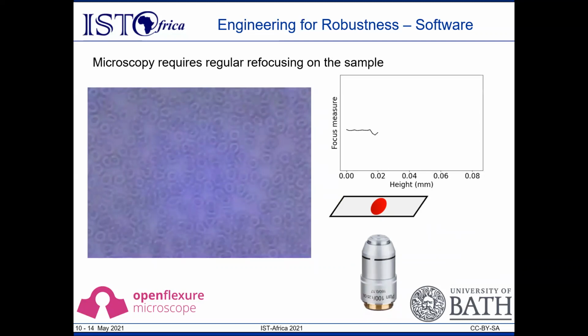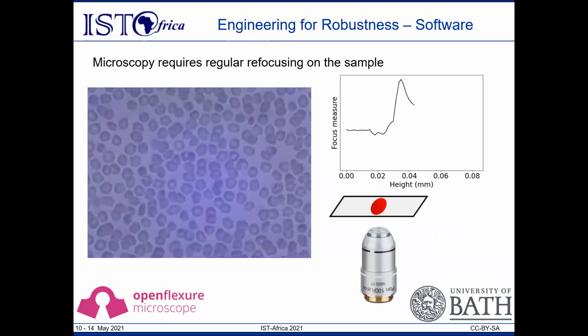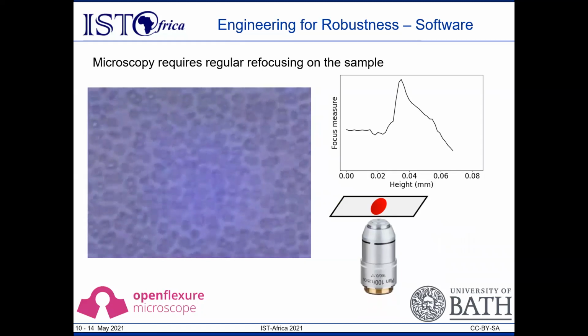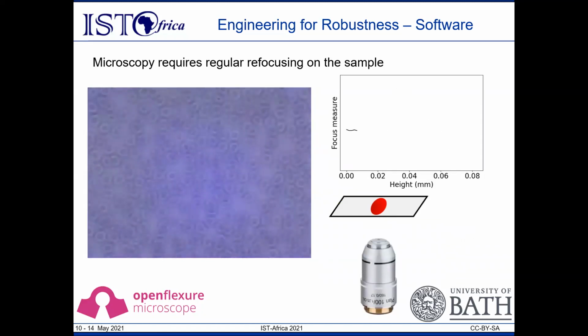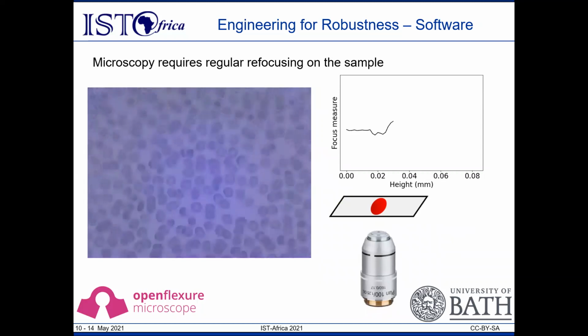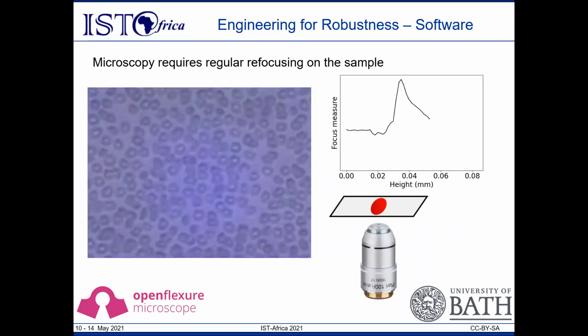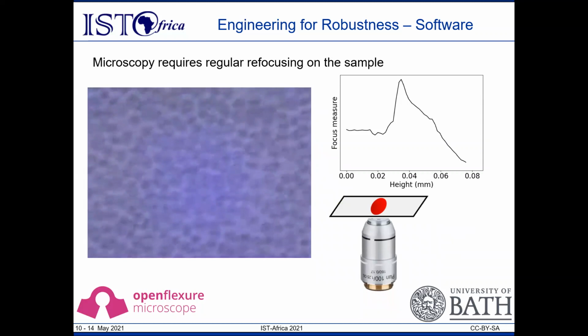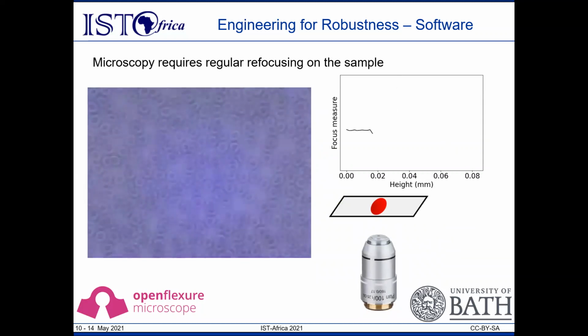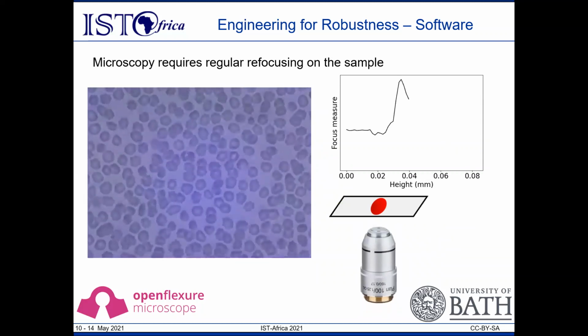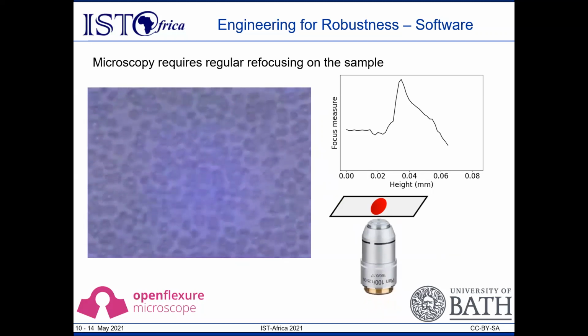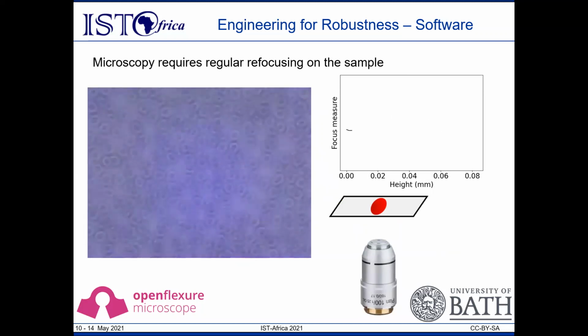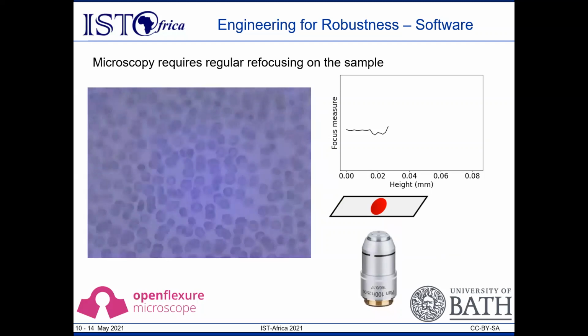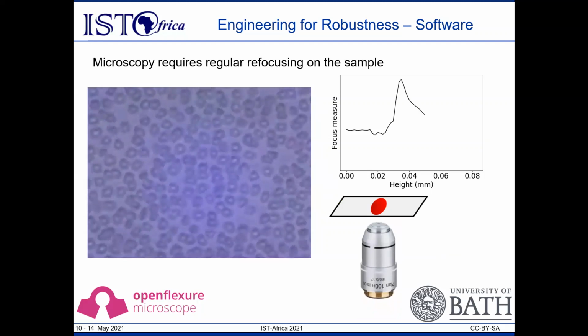And an automated microscope needs to be able to replicate this process, moving the optics compared to the sample to maximize the sharpness in the image. With the 100 times magnification objective that we use for blood scans, the range that the microscope is fully focused in is less than a micron, or 1/1000th of a millimeter. This is where the precision stage of the OpenFlexure microscope becomes essential.